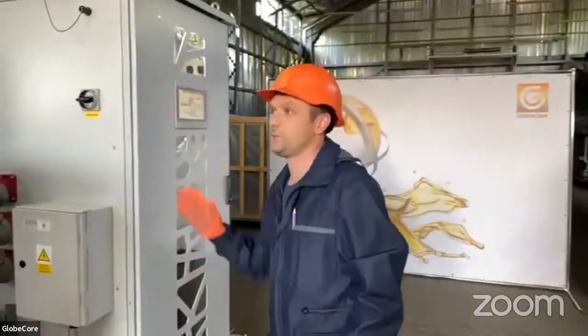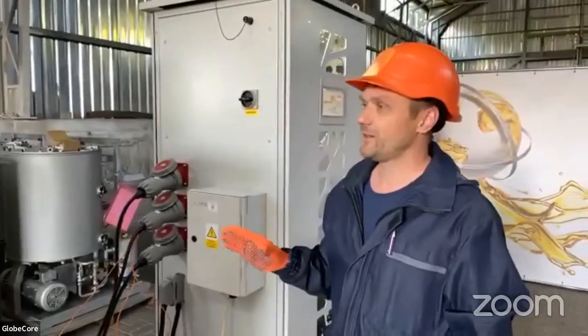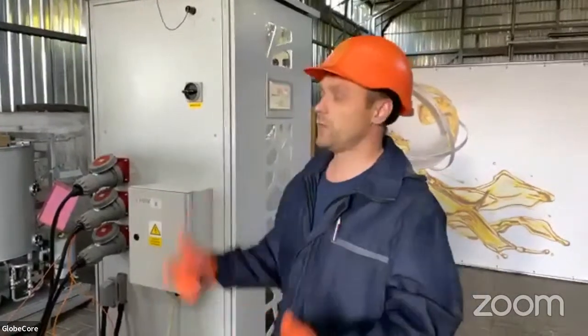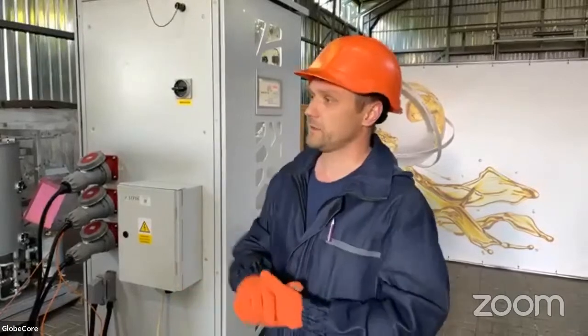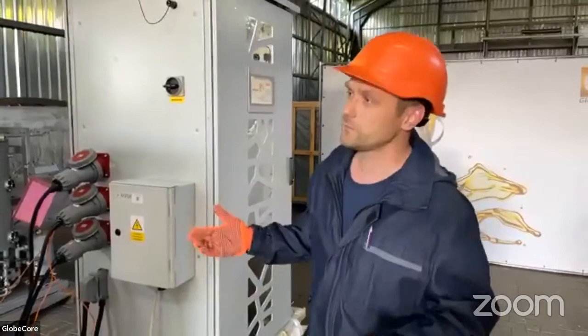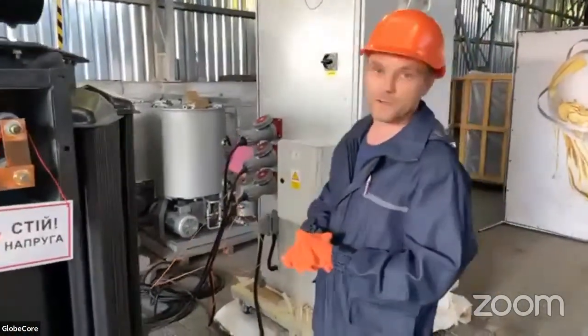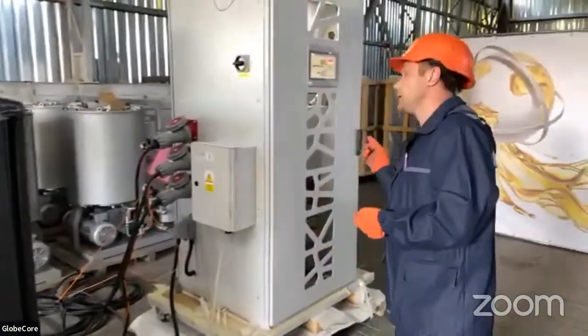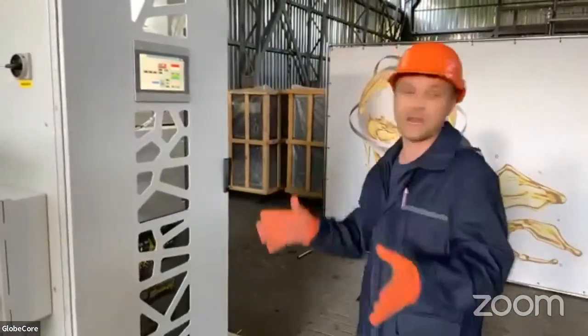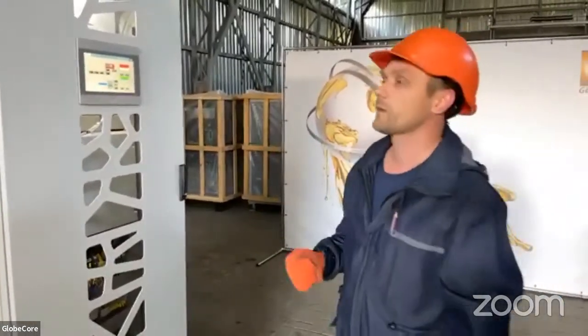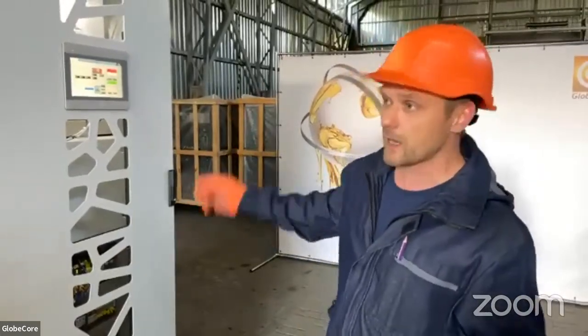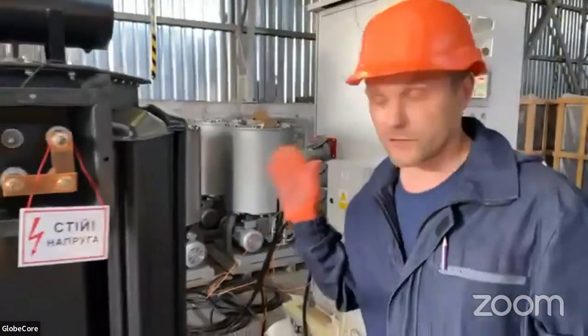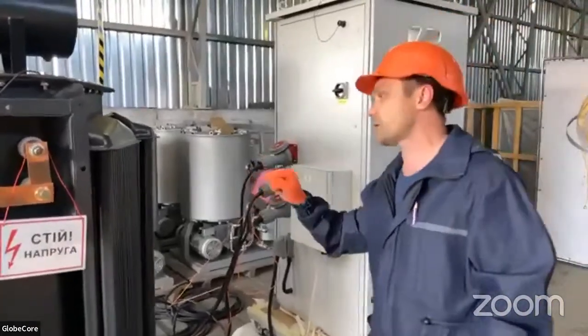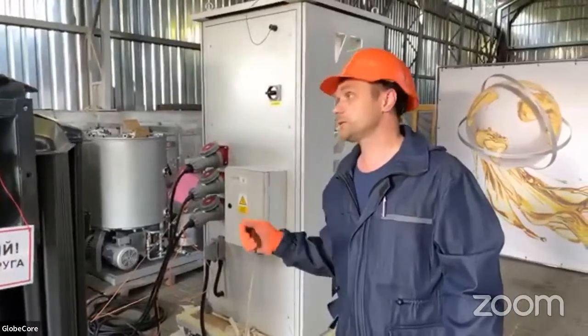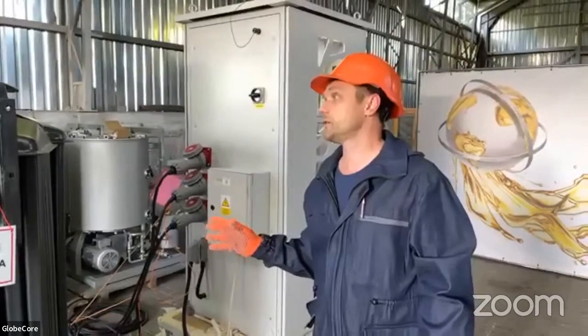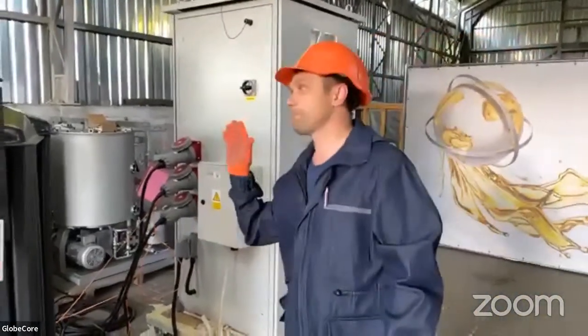A few words about this system. It enables us to apply heat directly to the place where it is needed. So by heating the windings, we heat solid insulation, and it helps to extract water from it very effectively. So the operator can set the time of the process and the parameters of the transformer. As the parameters are set, the heating process starts, and when the temperature is reached, it is maintained, and in cycles, the resistance of the winding is measured, and from this, the temperature of the winding is obtained. So we control the temperature of the winding.